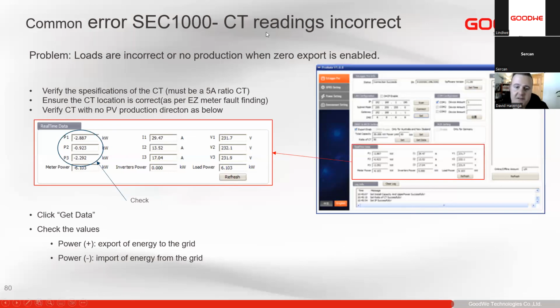But in this example here, you'll see there is something else that we need to have a look at. Because this power that it's displaying here for us is only active power, it does not display the reactive power for us. But if we do a simple calculation, we take our current times our voltage, it doesn't come nearby to this. The current times the voltage should be within 20% of the values we see here. Unless we have a very, very bad power at a premises, it's unlikely. So if you calculate this, this should be approximately 6 kilowatts. Yeah, we're seeing 2.88, 6 point something kilowatts.